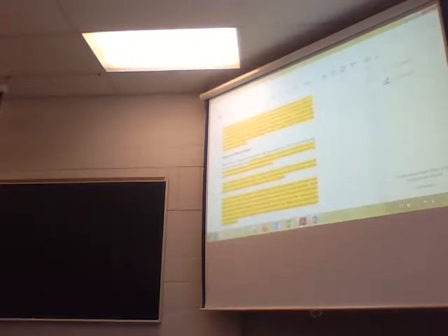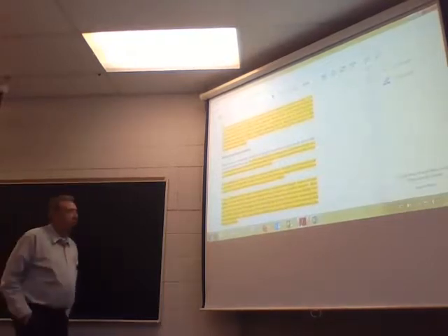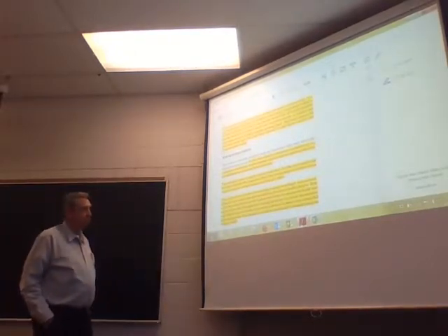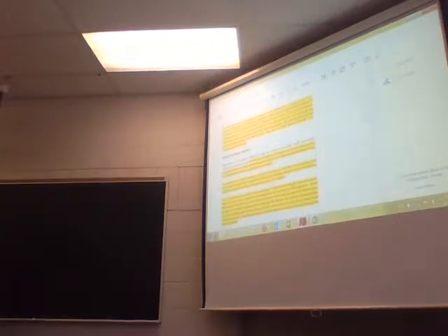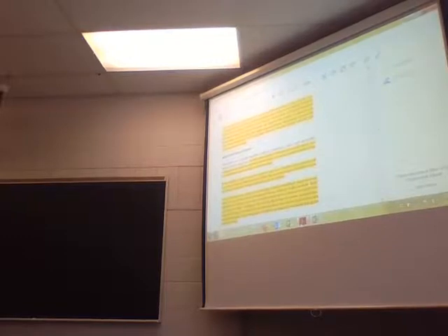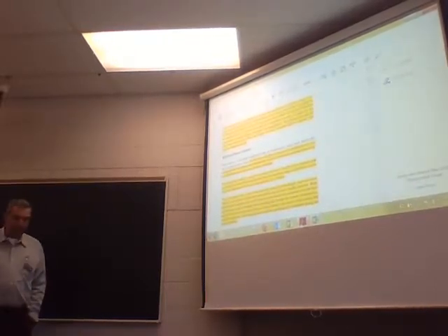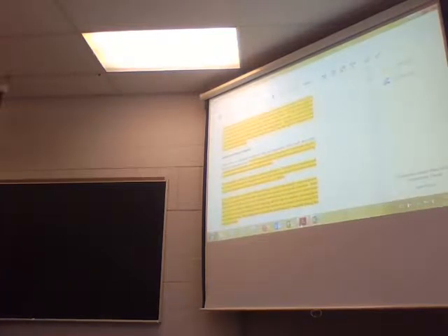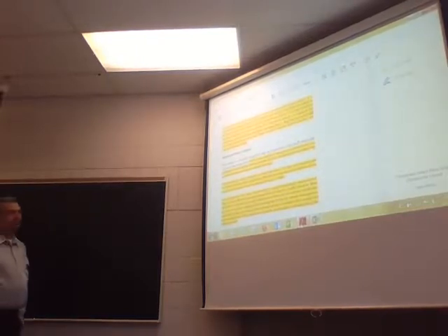Very common. All our little compressors at home probably have that. Two conditions make a stop-start control exceedingly uneconomical. That's Dutch for expensive. One is when there's almost a continuous demand for air. If you have a continuous demand, you don't really want to use stop-start because it's on and off all the time. It's quite the wear on it, and every time the motor starts, the current spikes. Correct, exactly. So you're going to take a heck of a lot of dollars out of your pocket.